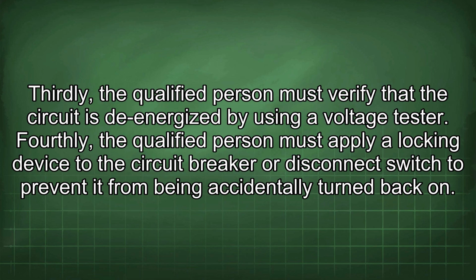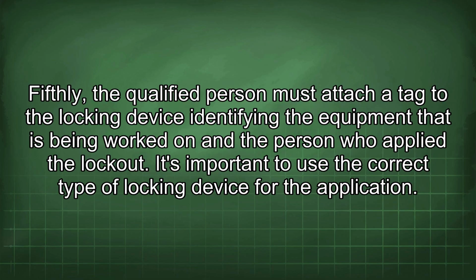Thirdly, the qualified person must verify that the circuit is de-energized by using a voltage tester. Fourthly, the qualified person must apply a locking device to the circuit breaker or disconnect switch to prevent it from being accidentally turned back on. Fifthly, the qualified person must attach a tag to the locking device identifying the equipment that is being worked on and the person who applied the lockout.